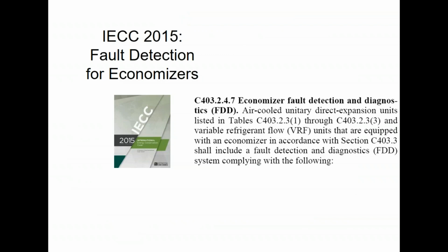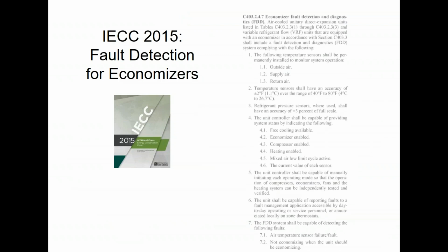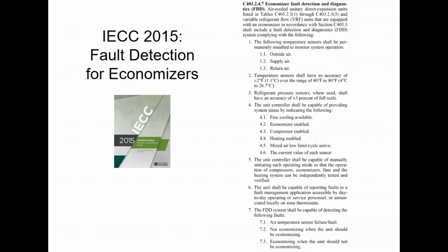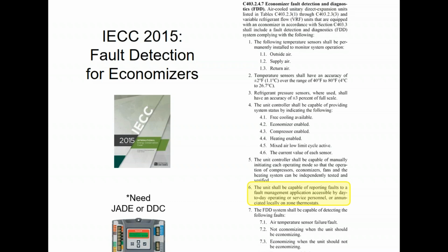We did talk about that last week as well, which is kind of a little bit of a repeat for the controls guys this week. That is required by code. There are numerous things that your economizer controller, whether it's a DDC controller or a Jade or a Belimo Zip or whatever it is, has to babysit. Make sure you don't have excess outside air, excess return air, make sure your temperature sensors are not all out of whack, things like that. So it's babysitting itself per the spec here in the code, and then it has to report those alarms back to the building automation system. The economizer controller shall be capable of reporting faults to a fault management application.